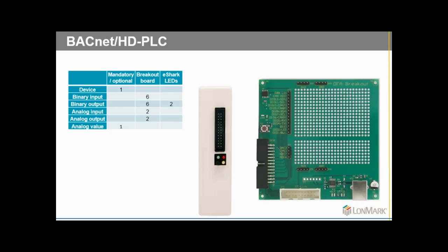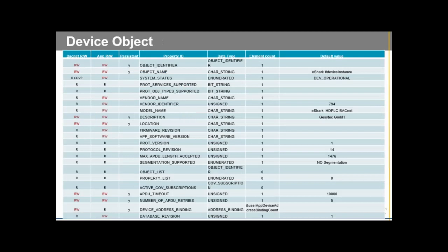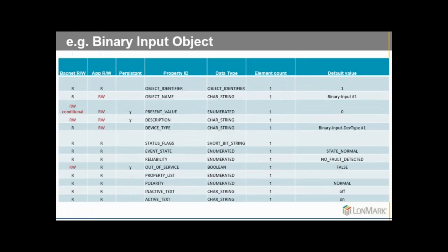So on our evaluation board, we made a device with smart actuators and smart sensors. You need to have a device object, some of the sensor objects. This is what we put inside of the object definition for the device objects. As a sample, binary input object. So we walk through all of the painful object definition if you are making code for that. That was the first time I really loved LONWorks again after a long time, because using Node Builder is much easier compared with implementing a BACnet device.